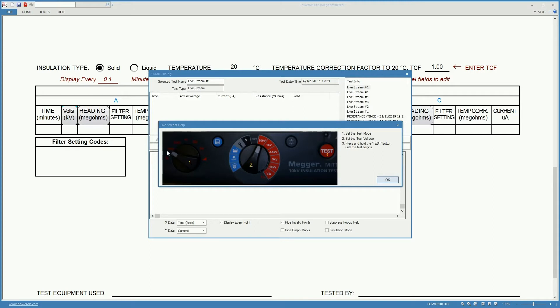This shows this screen which gives us instructions on what to do. Use this dial to select the type of test - insulation resistance over time in this case. Use this one to select the test voltage.